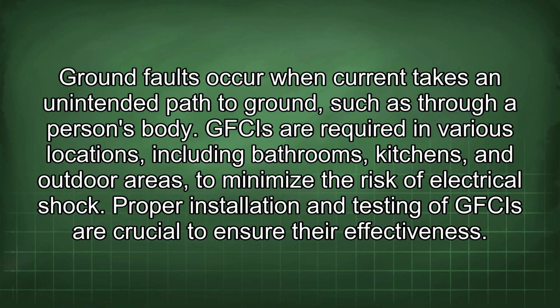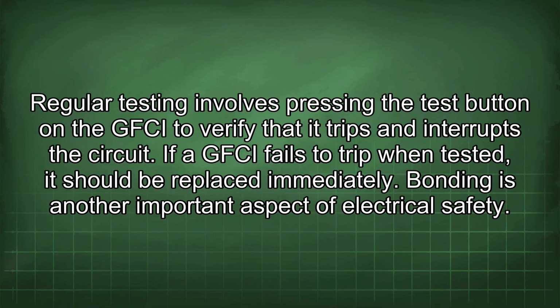Proper installation and testing of GFCIs are crucial to ensure their effectiveness. Regular testing involves pressing the test button on the GFCI to verify that it trips and interrupts the circuit. If a GFCI fails to trip when tested, it should be replaced immediately.